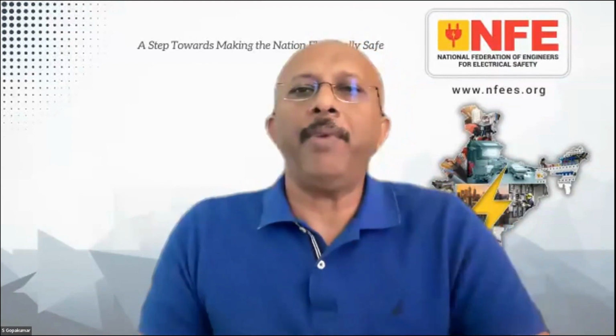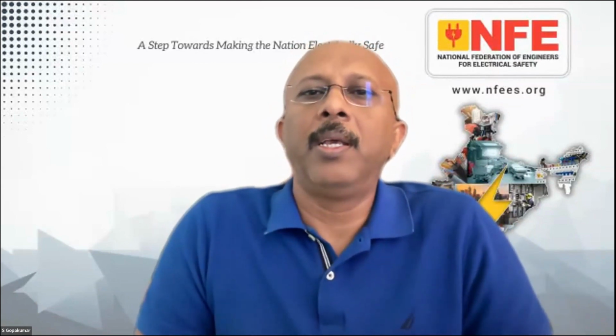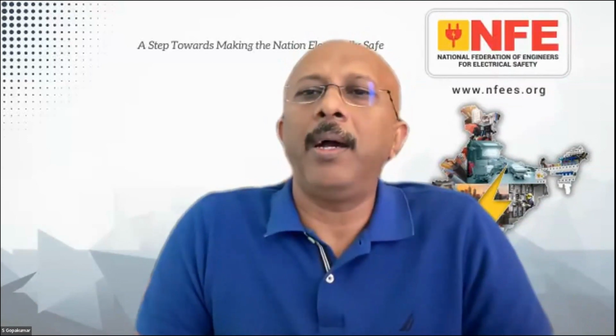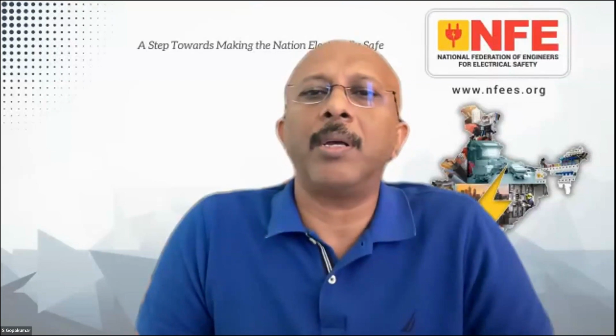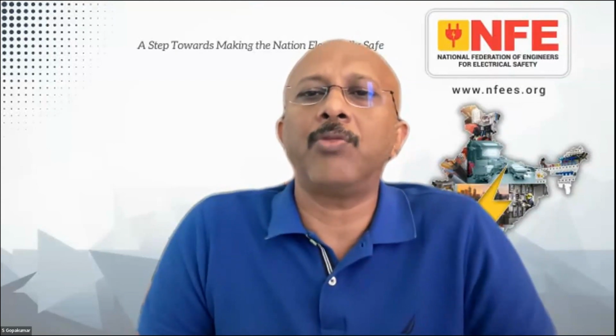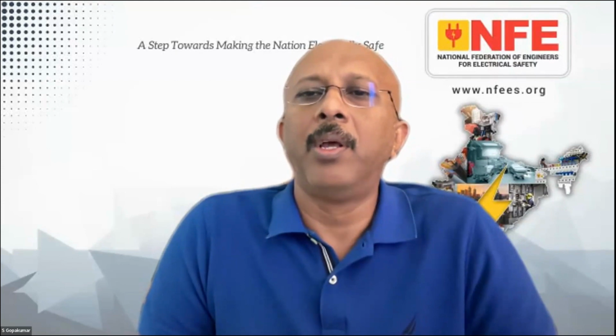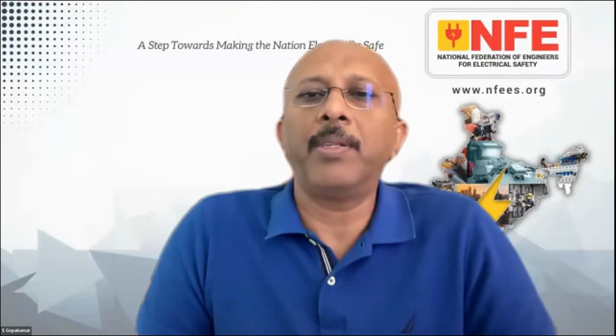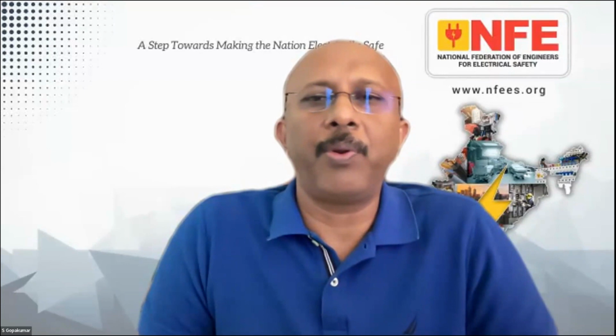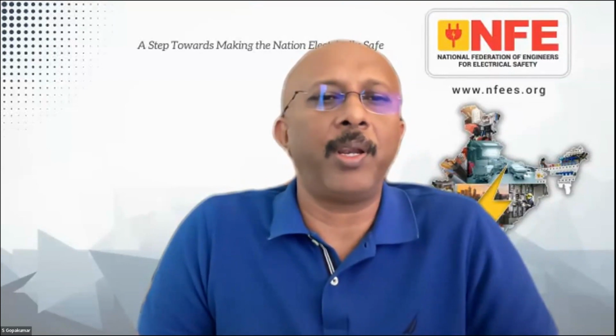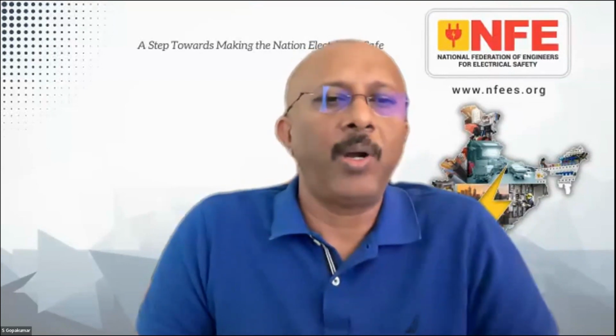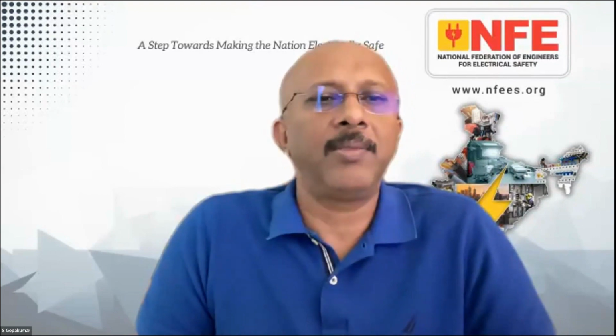So we have another interesting question. In a TT system, which is common in India, when the measurement of fault loop impedance is done, earth electrode resistance comes into the picture. Hence, we can say that even though measurement of earth electrode resistance is not important, maintaining a low resistance for the earth electrode is important, so as to keep the fault loop impedance low. Hope, Mr. Peter, you are able to see the question. You can read the question. So, would you like to answer this?